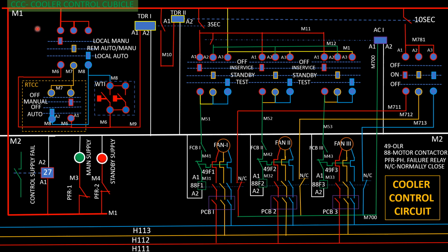When control is on auto mode and the pointer of the WTI, winding temperature indicator, reaches a certain preset value, that is 60 degrees centigrade or 65 degrees centigrade, the mercury switch tied with the pointer of the WTI will tilt to make a circuit to switch on the cooler system automatically. This is the mercury switch connection of the WTI.